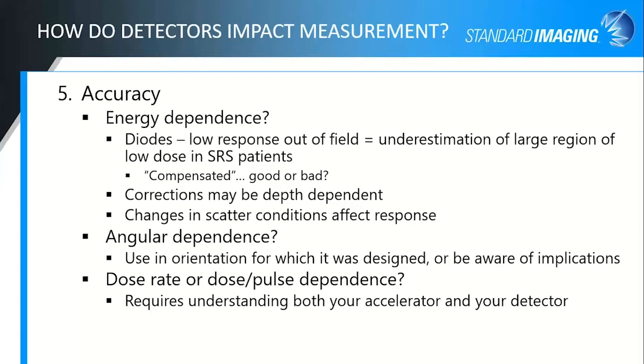Accuracy of your detector is also critical for scanning, just like it is for output measurements. You need to understand the energy dependence. Diodes often have a low response to low energy, and so they can under-respond out of the field and give you an underestimation for the low dose region, especially in your SRS patients as you're scanning these small fields. I mentioned the compensated diodes. Here's where you really need to think about whether this is really fitting what you want to measure, or whether it is making it more complicated and not going to help with your measurements. Corrections may be depth dependent, particularly for a detector that has a higher energy dependence. That energy changes as you increase your depth with your scan. So that would affect your PDDs maybe a little bit more than your profiles, except out at those tails where, again, you get a different spectrum, but something to be considering as well.